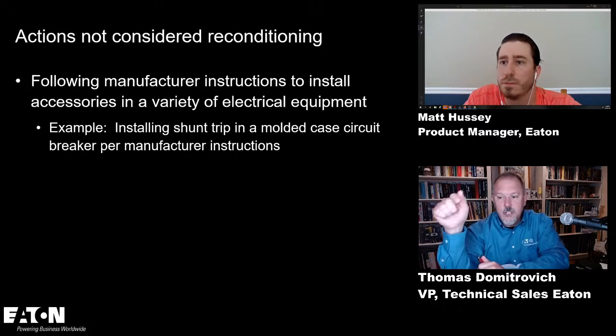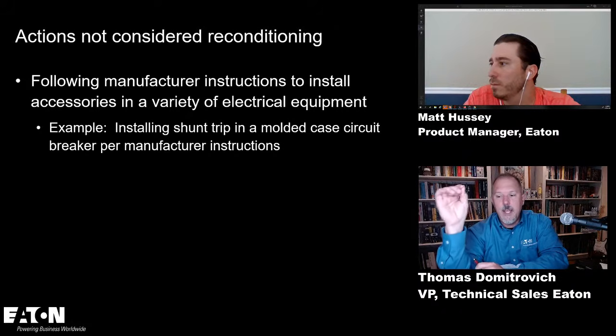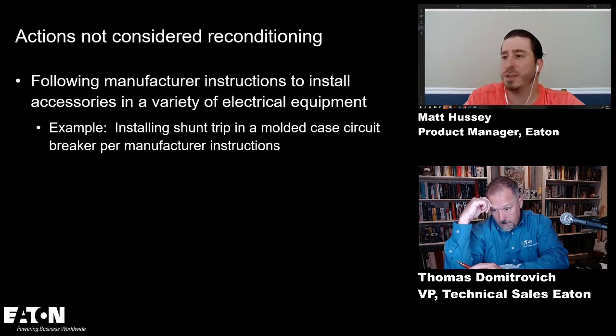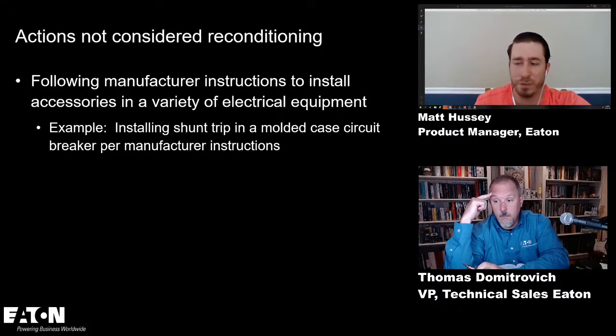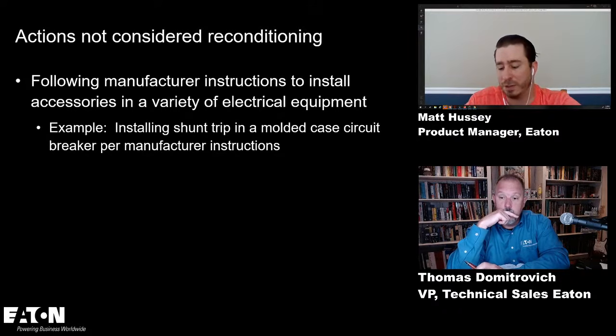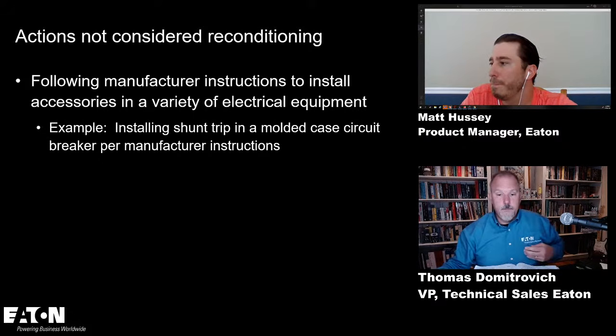So looking at some of the questions, Felix asked, are buckets in the MCC considered each a separate enclosure? I think you could say that that's the case because each one is defined as its own compartment, which you've got a door and a unit all constructed together. Granted, they're all installed in a complete lineup with multiple vertical sections. I'm sure when we test it for enclosure type classification, it's assuming all the rest of the doors and things are closed up. So I think you could look at it as the entire lineup being the overall enclosure, but then you have each unit representing each compartment. Yep. Perfect. All right. Let's move on.